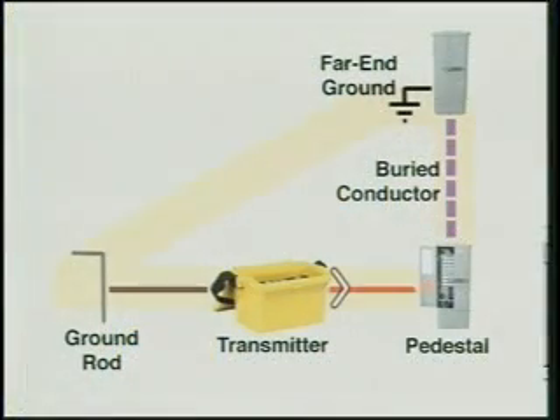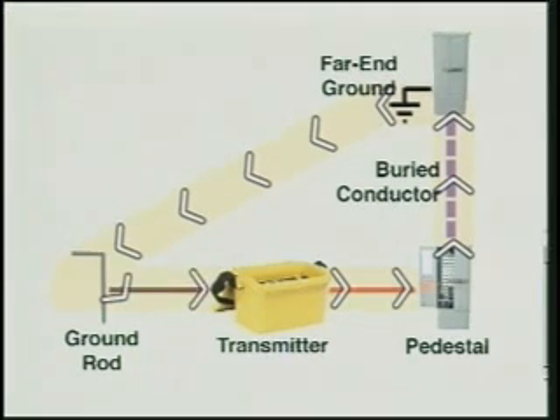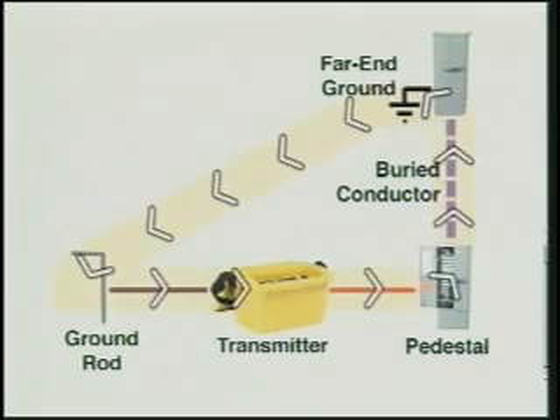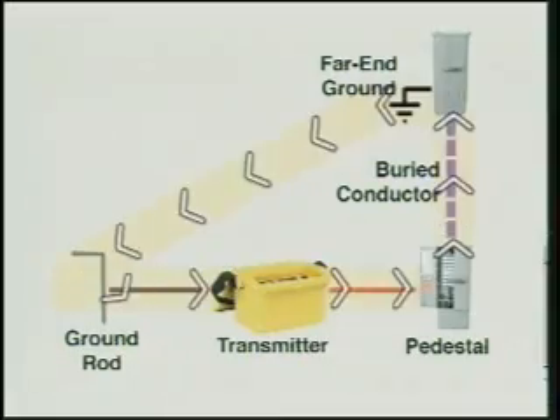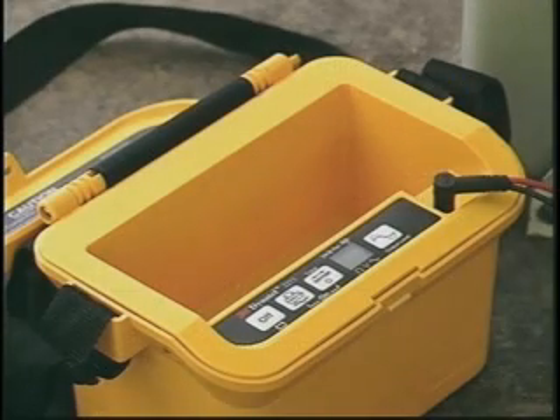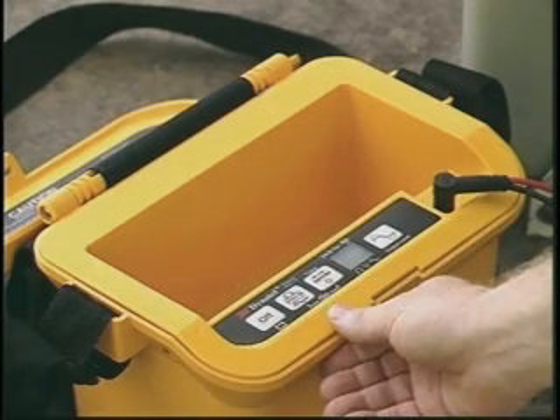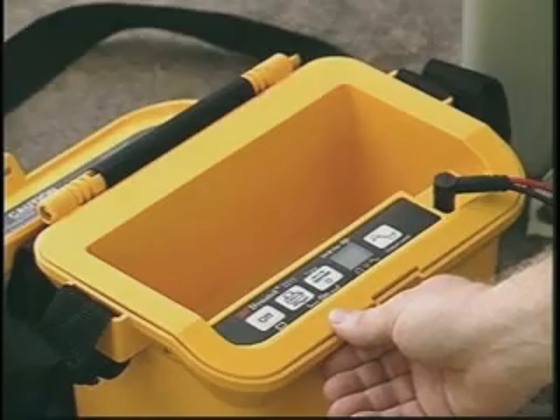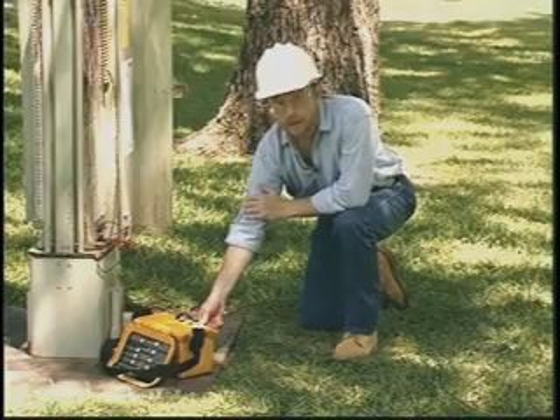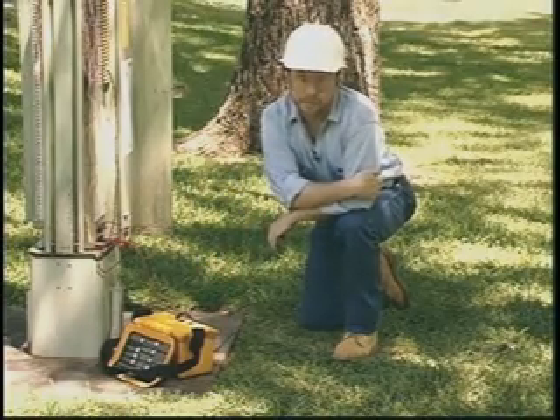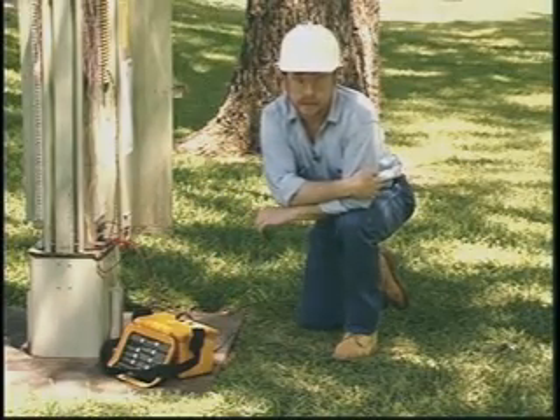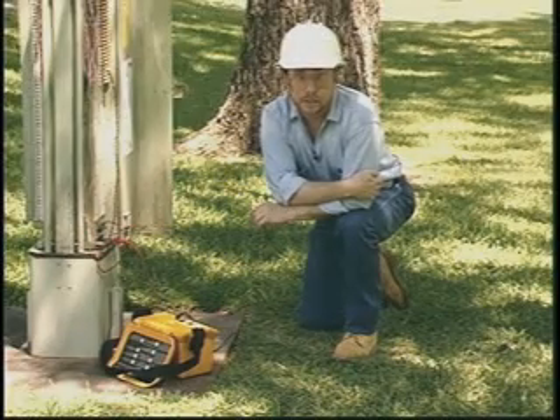Successful location of a buried conductor using the direct connect method requires a complete circuit. The circuit goes from the transmitter through the conductor back to the transmitter through a far end ground and the ground rod. To test the circuit, press the ohms key. You should hear a solid tone like this, indicating the circuit is good. A beeping tone means you have a marginal circuit. A no tone means the circuit has a high resistance or is open, and the transmitter may not be able to apply enough signal for tracing.